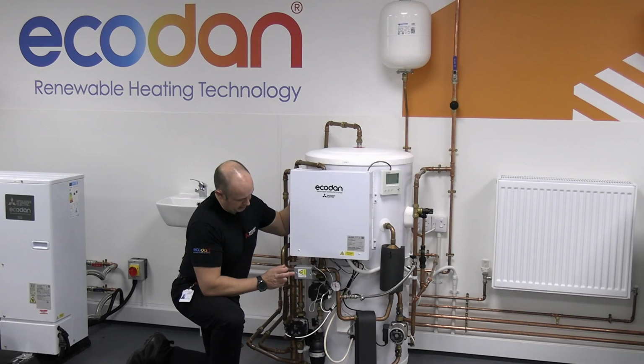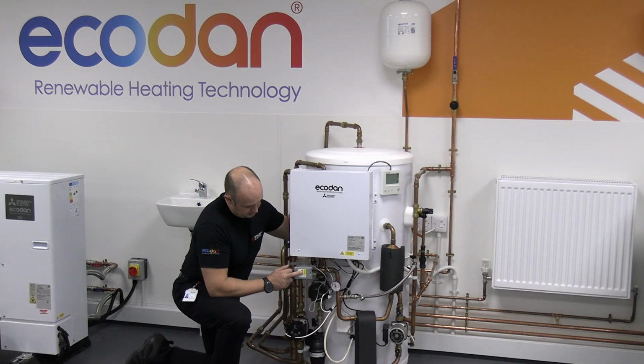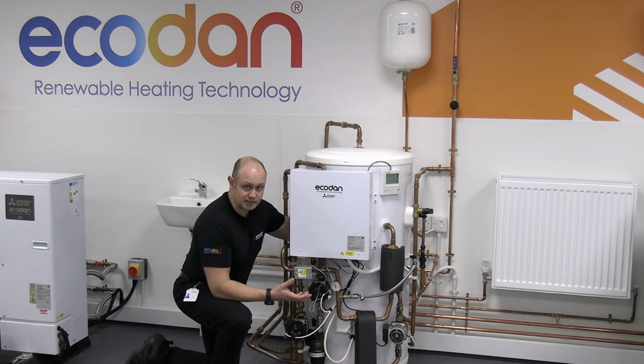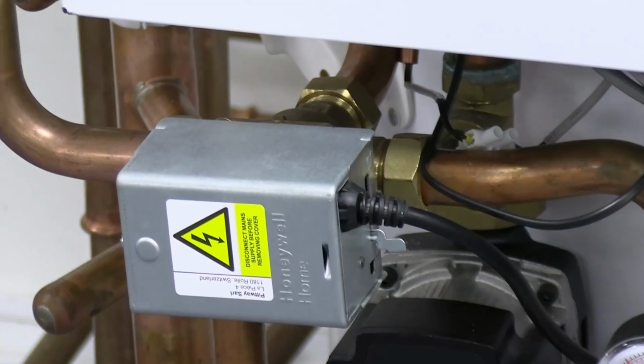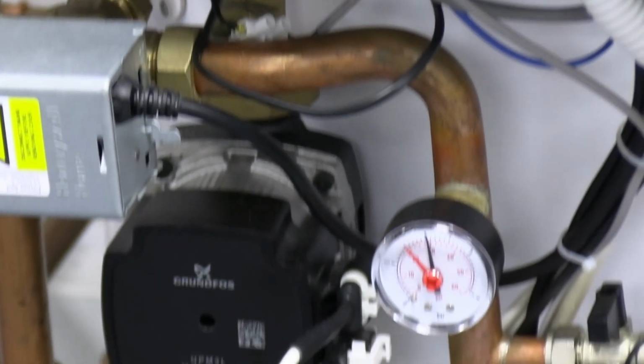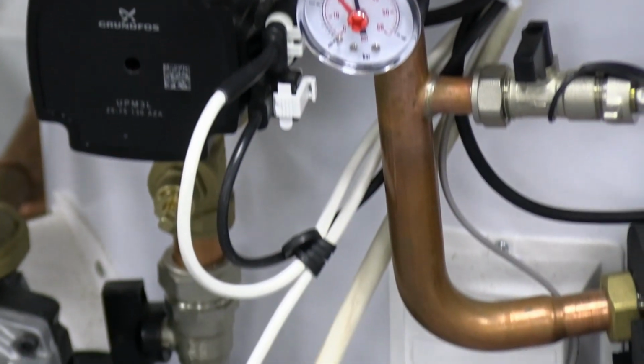Follow up, we come up to a 3-port valve. So that allows me to do hot water or heating. Hot water takes priority. Carry on doing hot water until either the cylinder's been satisfied or we put a time limit on there, which you can do via the controller. We follow it through. From there, on the hot water side, we come down to an external plate.